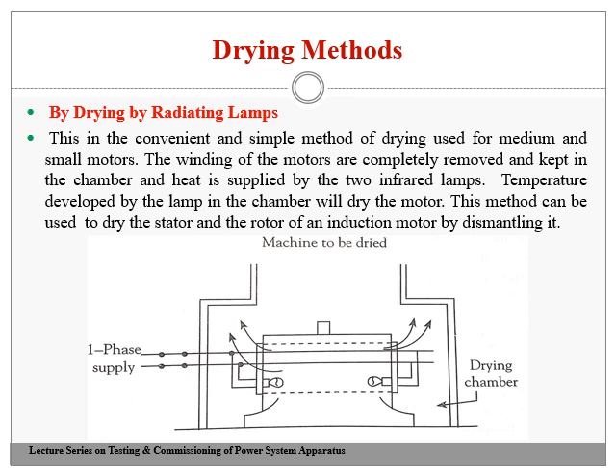This is one method. Let us go for the second one. It is drying by radiating lamps. In this case, once again, we'll have a heating chamber. We take the induction motor, with both end covers removed, and this chamber will be provided with bulbs. You can see the bulbs. For this one, the single phase supply will be given. As you know, whenever an incandescent bulb glows, we get heat energy. That heat energy is similar to what you have seen in the previous drying method. The heat developed will remove the moisture content which might have been absorbed by the insulation provided in the rotor and the stator winding of the motor.